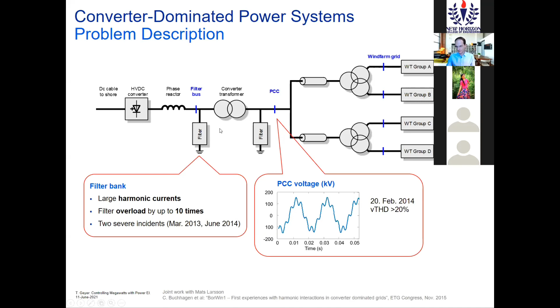When you do a harmonic analysis and model the system in detail, you have the frequency here and the gain from a wind turbine, from a certain voltage harmonic, to the current it drives in the filter. At certain frequencies, a couple hundred hertz, you get a spike. That means if the wind turbine injects a harmonic at that point, it will drive a significant harmonic current in the filter bank. So that's something that became clear.